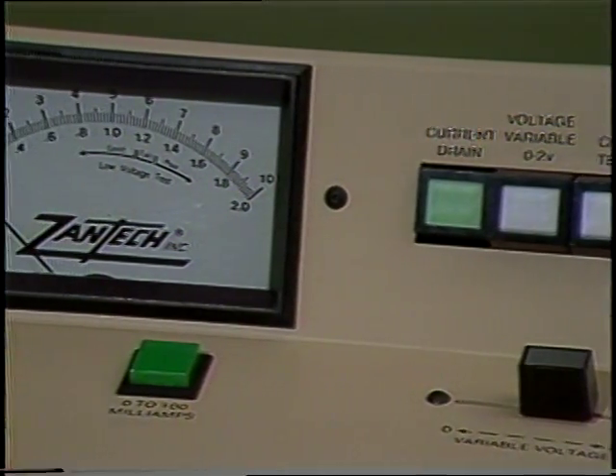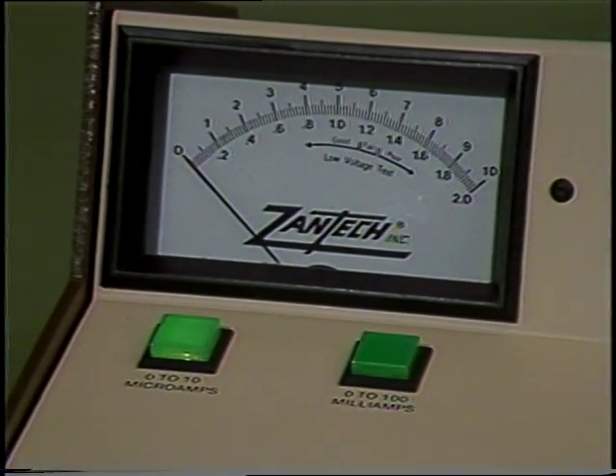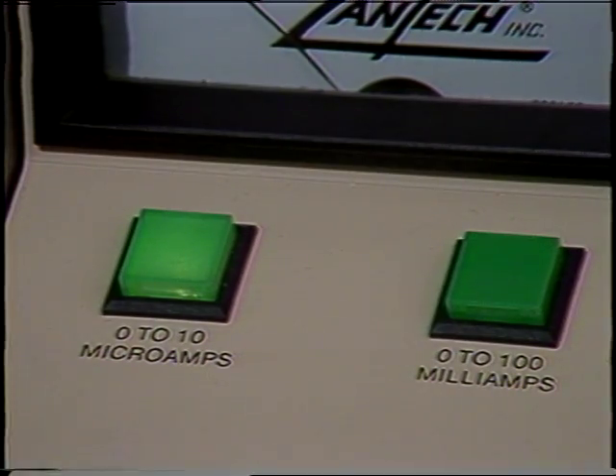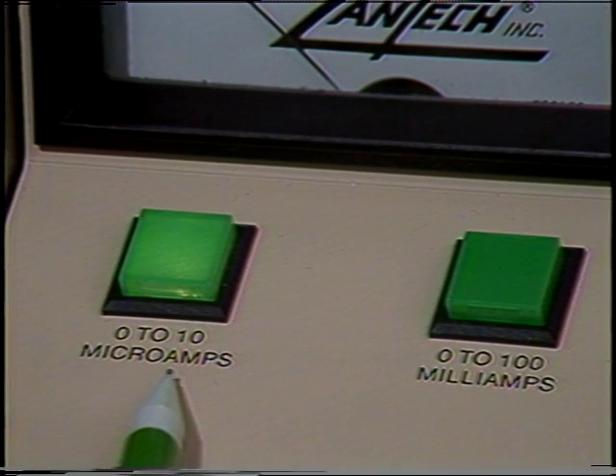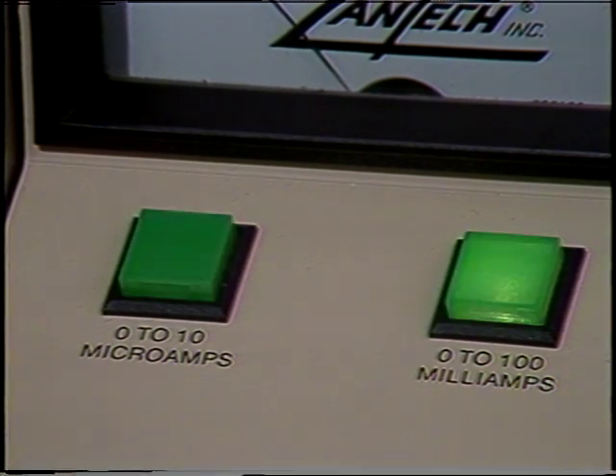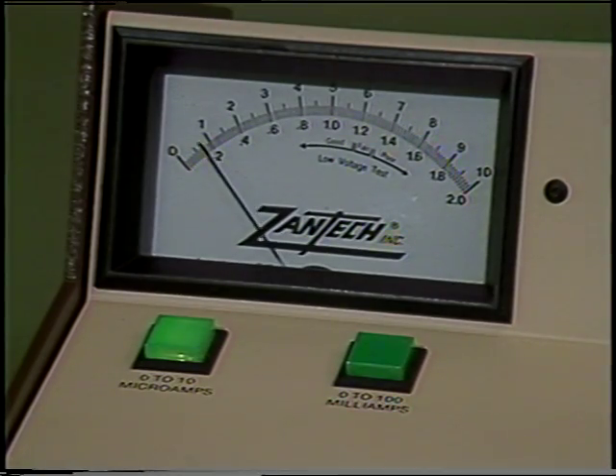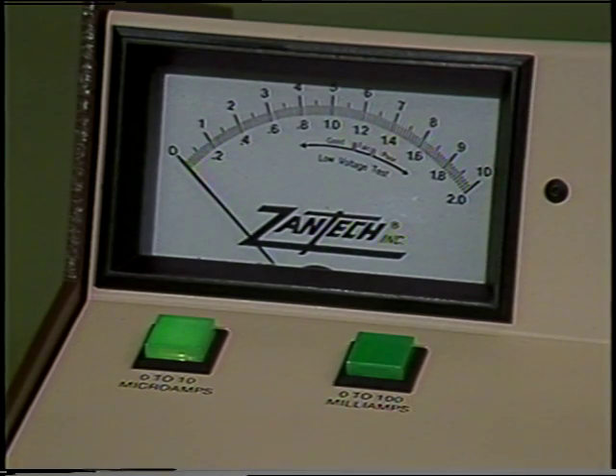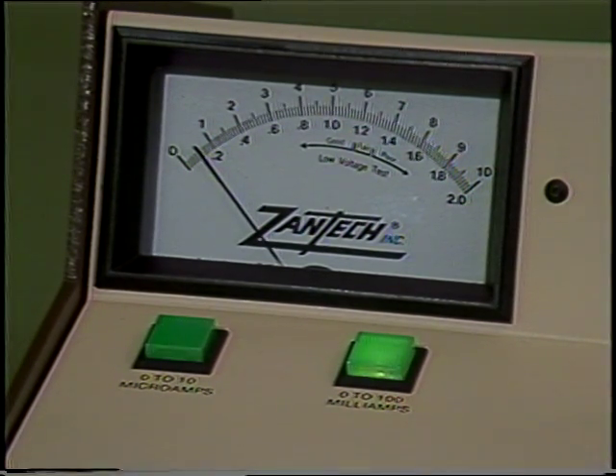There are 2 current ranges on the ZA900. The low current scale measures from 0 to 10 microamps. This covers the normal operating current drain of any quartz analog or quartz digital watch. The high current scale measures from 0 to 100 milliamps. The model ZA900 automatically changes to this scale when the current drain from the movement is greater than 10 microamps. The pilot lights under the meter indicate which current scale to read.